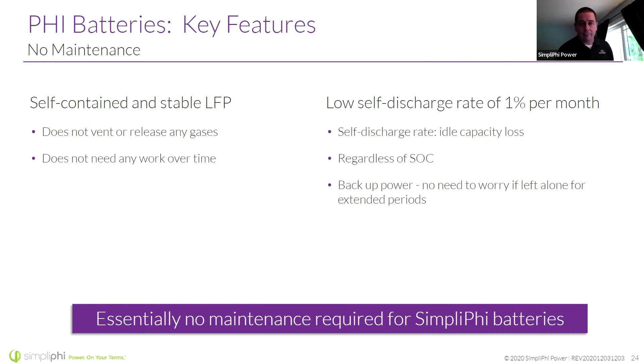It also has a very low discharge rate of about 1% per month, with the breaker off and in storage. We ship at about 30% state of charge, so get your batteries fully charged up before connecting them to loads. But if you needed to store them for a year, go ahead and get them charged up to full, and they'll absolutely sit well for a year. You might want to continue to charge them maybe once a year or so, but at a 1% discharge rate, you can do the math -- you've got a long time before they discharge themselves all the way.